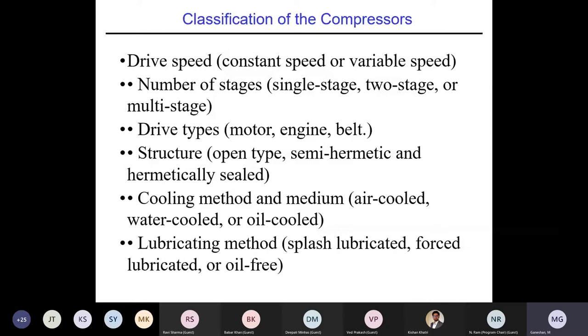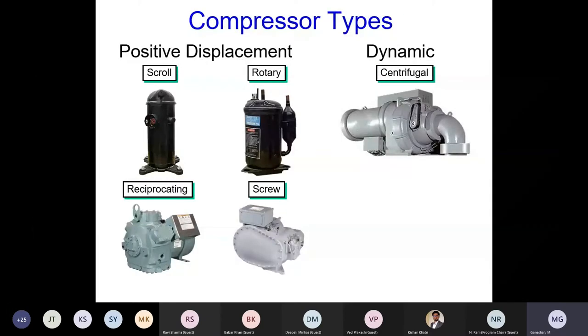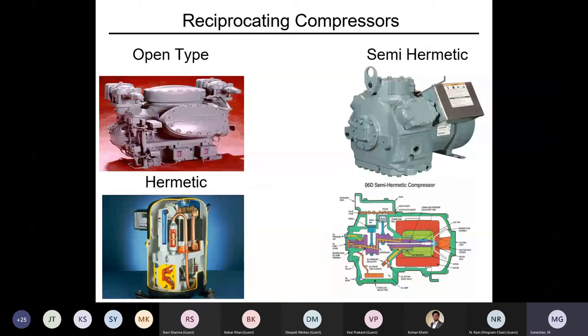How is it structured? Is it open type, semi-hermetic, or hermetically totally sealed? Yeah, I can also classify it by cooling method: there are air-cooled, water-cooled and oil-cooled. Then you can classify it further by lubrication method, like a smaller unit with splash lubrication, then forced lubrication, and now the current scenario with an oil pump. These are some of the types: scroll, rotary, centrifugal, reciprocating, and screw. This is the old veteran with the open type, direct driven, or the semi-hermetic with both coupled together, and hermetically totally sealed, but that is a reciprocating.